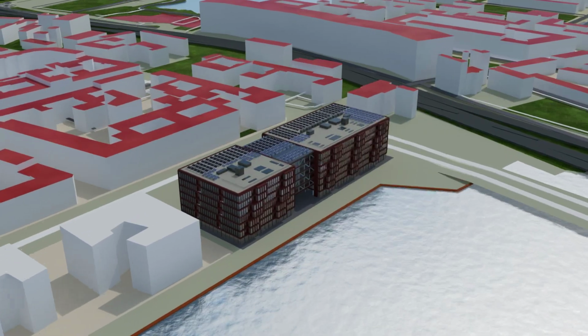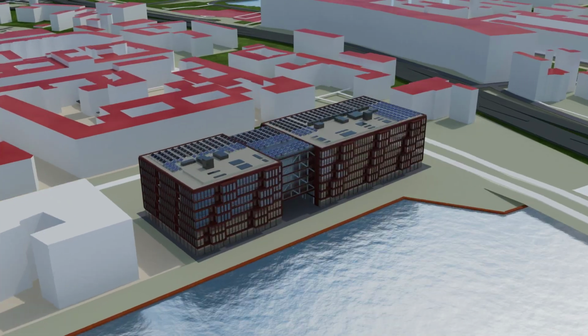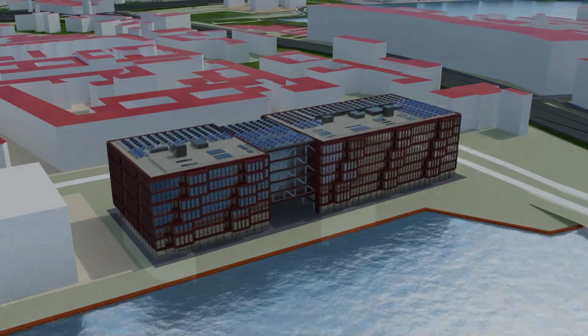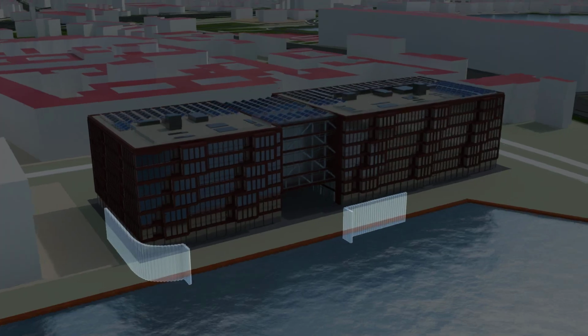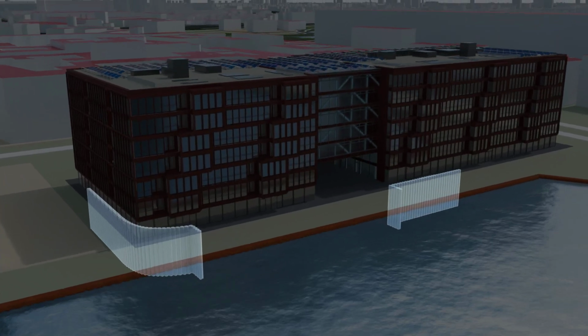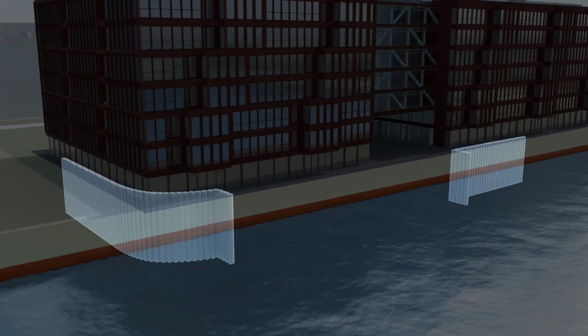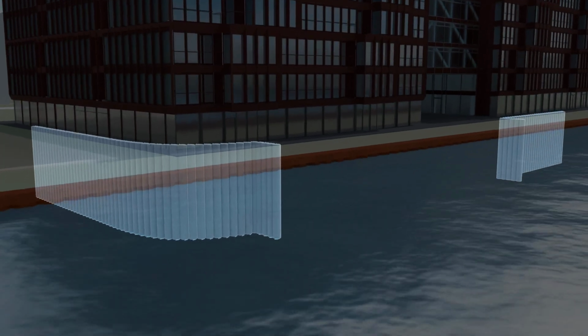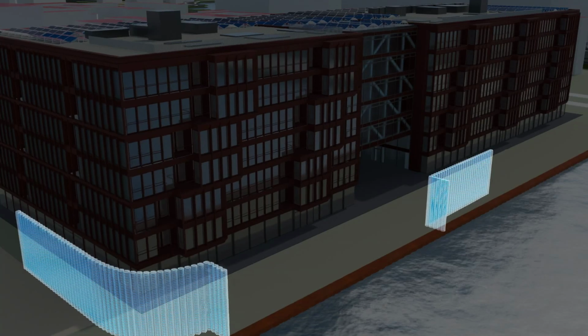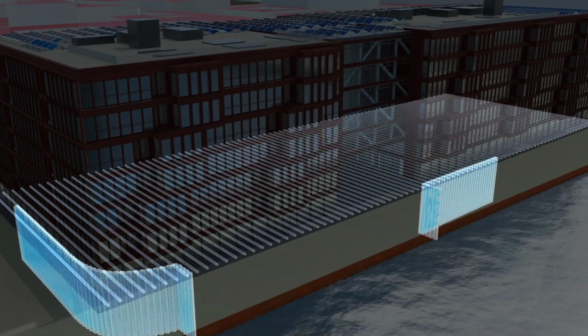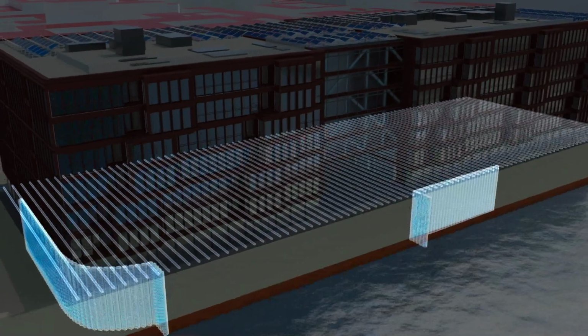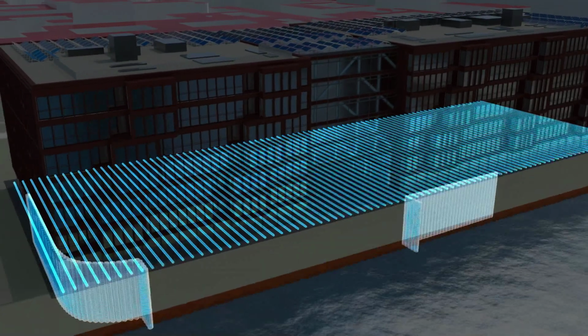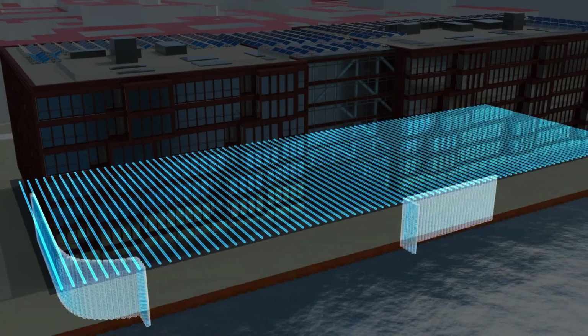The cooling energy from the ice is needed for the summer. On the first warm days of the year, the cooling will come out of the ground. Around 100 concrete piles have been bored on one side of the building and on the banks of the river. The pilings are there for stability on the otherwise sandy ground, yet inside these pilings are pipes filled with water. There are also many thin water pipes under the floor slab of the building. Circulation pumps transport the coolness of the underground water into the building.